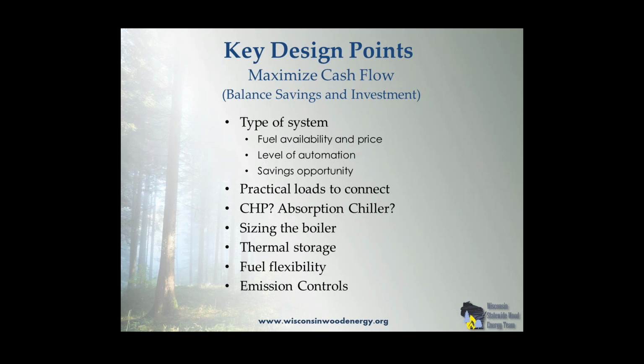The new boiler MACT rules, area source rules for units that are under 10 million BTUs an hour of input, require different kinds of control systems than units that are over 10 million, and they can make substantial differences to the cost of a project. The cost of an ESP, which is our preferred control method in institutional type settings because of the amount of labor and the work versus a baghouse, for a 300 horsepower boiler, it can add $200,000, $250,000 to the cost of a project. So emission controls are an important consideration when you're sizing and deciding on exactly what you're trying to accomplish with the system.